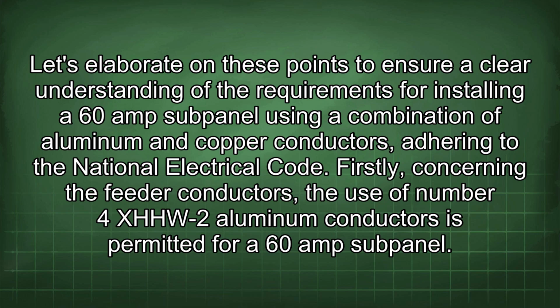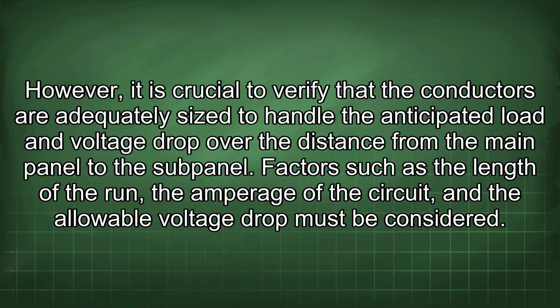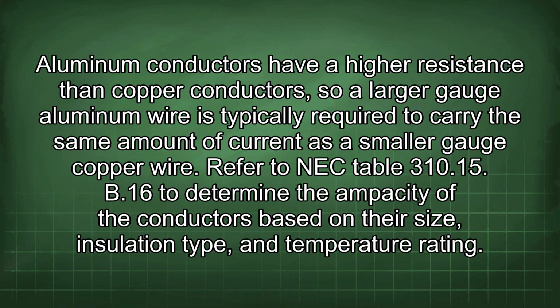Firstly, concerning the feeder conductors, the use of number 4 XHHW-2 aluminum conductors is permitted for a 60 amp subpanel. However, it is crucial to verify that the conductors are adequately sized to handle the anticipated load and voltage drop over the distance from the main panel to the subpanel. Factors such as the length of the run, the amperage of the circuit, and the allowable voltage drop must be considered. Aluminum conductors have a higher resistance than copper conductors, so a larger gauge aluminum wire is typically required to carry the same amount of current as a smaller gauge copper wire.